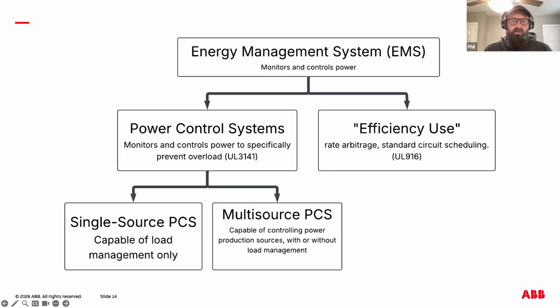So just as an overview, here's a hierarchy tree to better visualize the differences between EMS and PCS. The umbrella category of EMS is defined as a system that monitors and controls power. PCS is specifically for overload control. Single source PCS is capable of load management only, whereas multi-source is capable of controlling power production sources with or without load management.